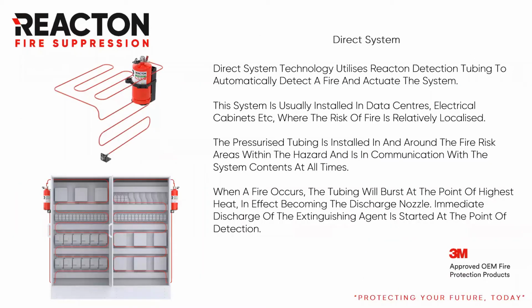So we offer two different types of systems, the direct technology system and the indirect technology system. Here we have the direct system, which is mainly for use within smaller enclosures where the fire risk is relatively localized. The direct system is a very easy to understand concept, where we have a pressurized cylinder housing the extinguishing agent, which is connected to a pressurized polymer detection tube.